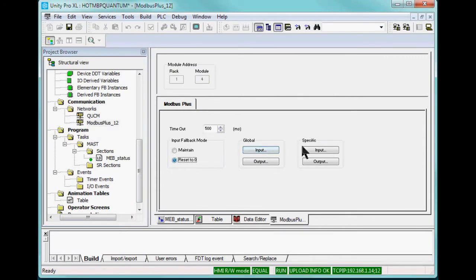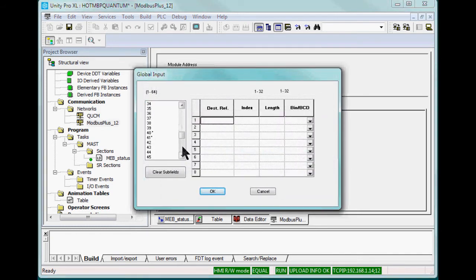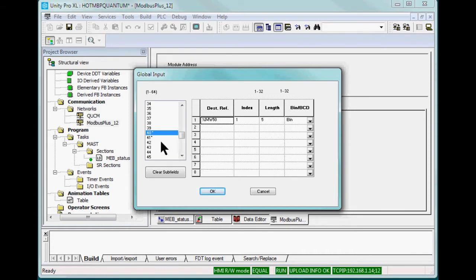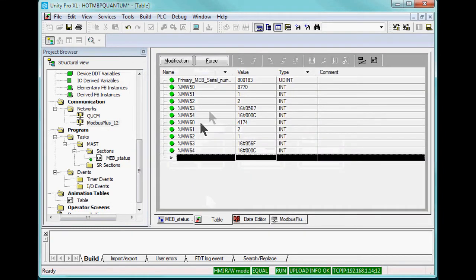Configuring the Unity PLC to subscribe to the global data is simple. In this case, the data from primary node 40 is mapped to %MW registers 50 through 54. The secondary node 41 is mapped to registers 60 through 64. Unplugging various cables show the real-time updating of these values.